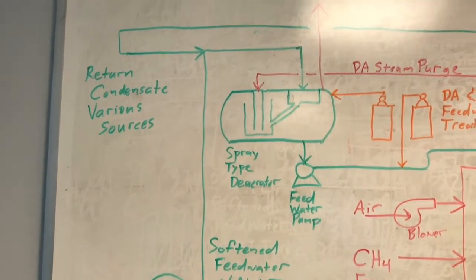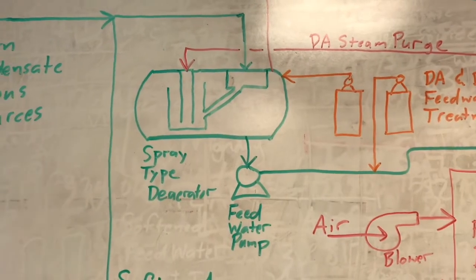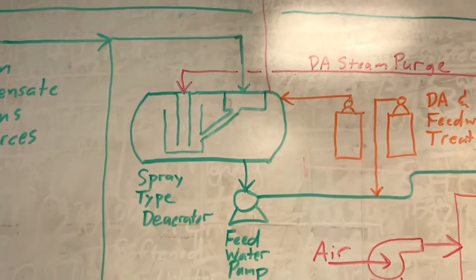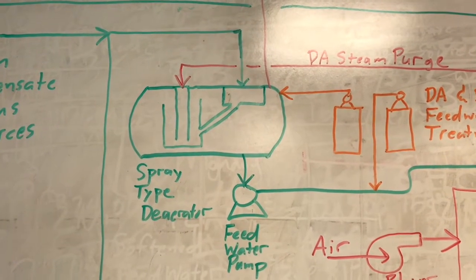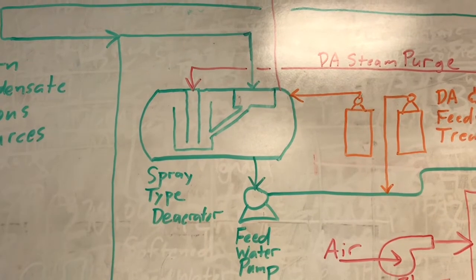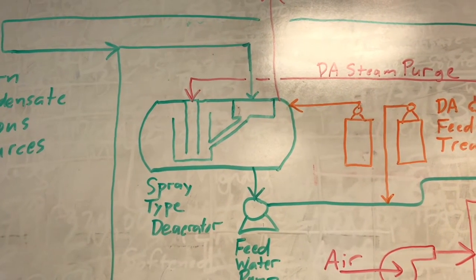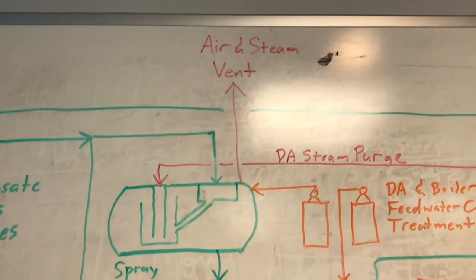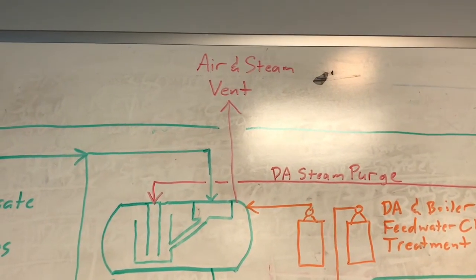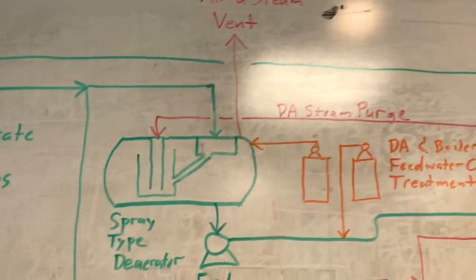From there, the softened water goes into what's called a deaerator. We have a spray-type deaerator, where the water comes into a tray-type system, drops down into what looks like a bucket, and is sparged with steam. The purpose is to heat up the incoming water to drive off any dissolved oxygen and carbon dioxide — which cause corrosion issues in boilers — through the vent. We'll get back to the steam purge later.